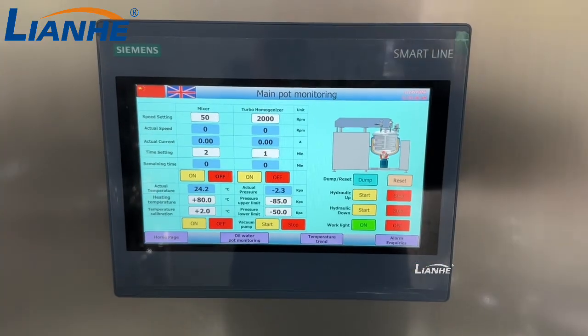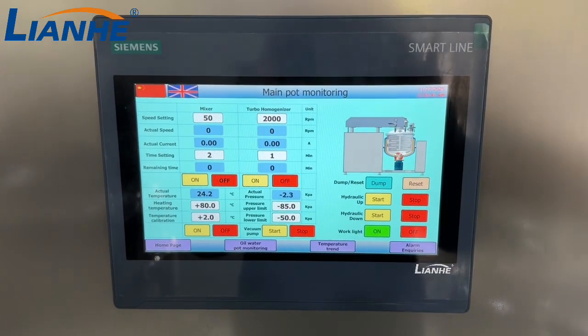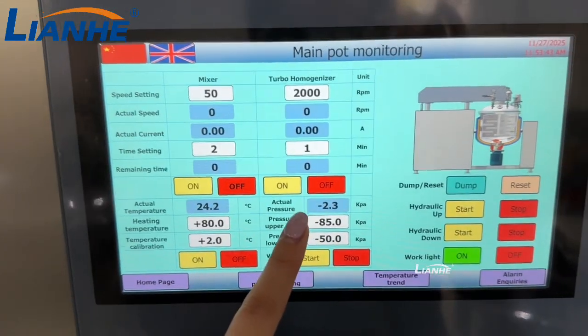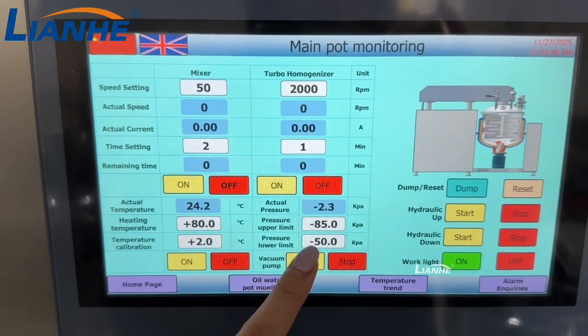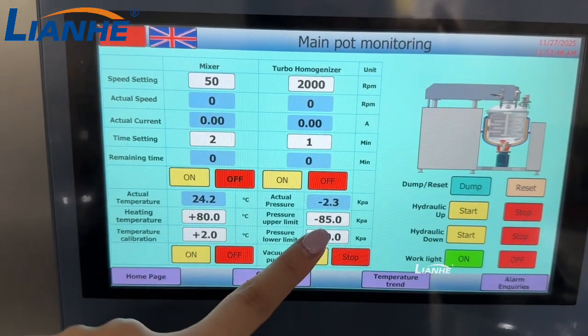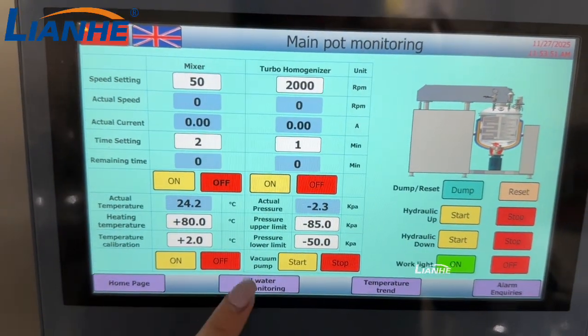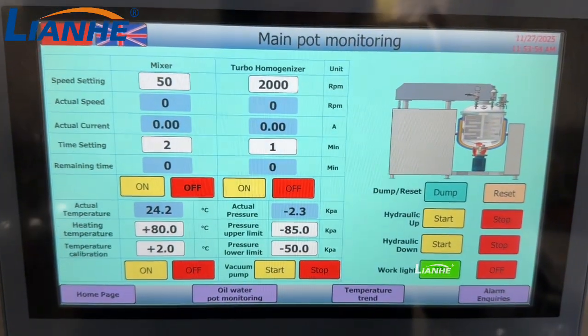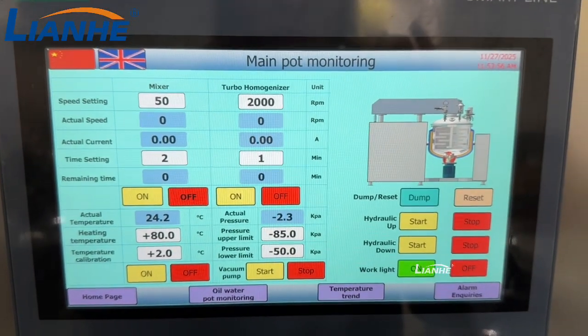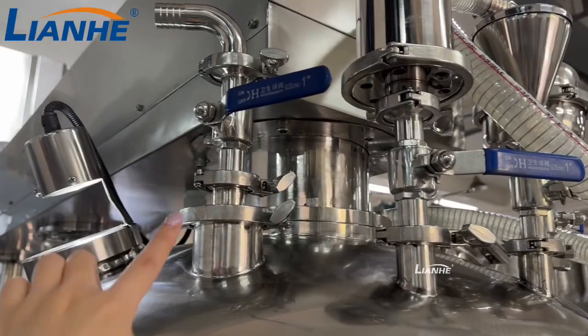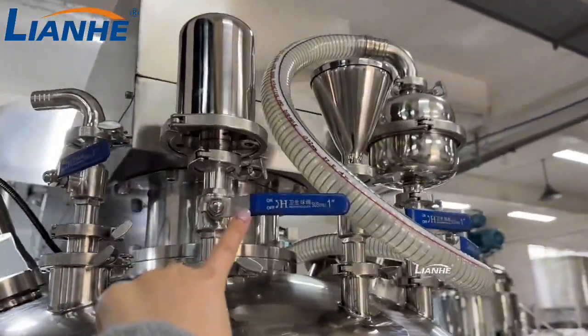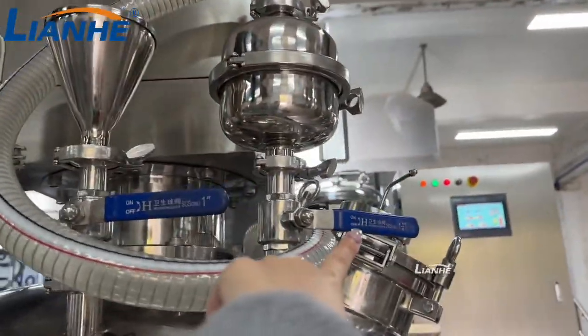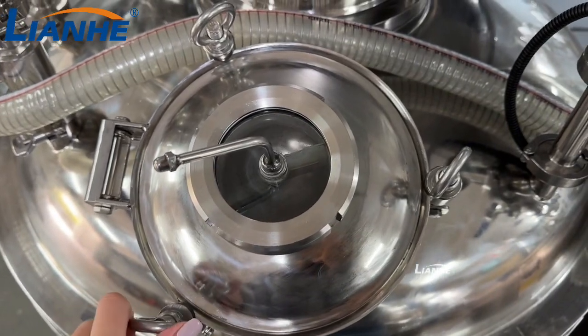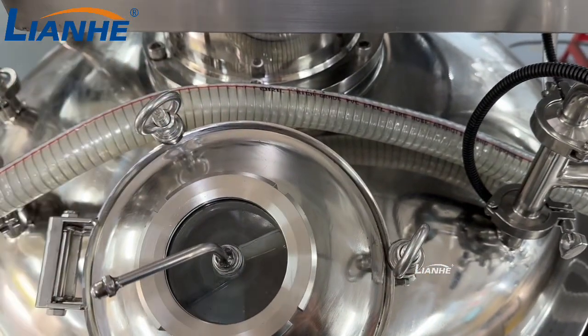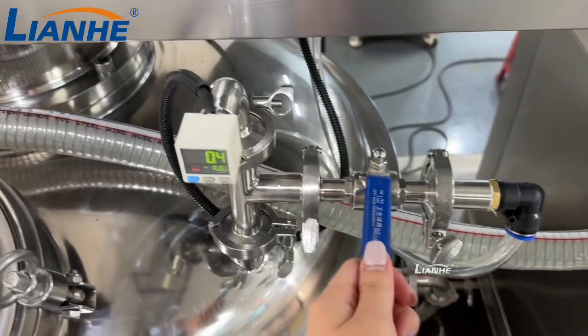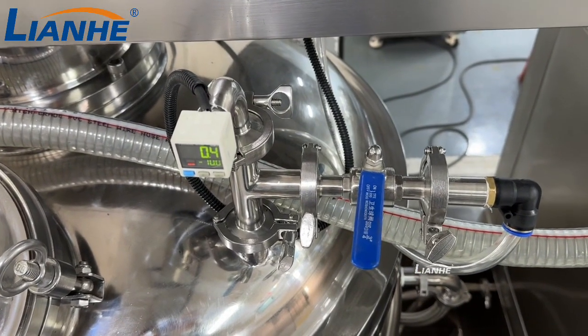And now we can test the machine's function step by step. First we can test the vacuum function. Now we already set the pressure of the vacuum, like minus 85 kPa, and the pressure lower limit is minus 50 kPa. And then we can check the valves. You may check these valves: closed, closed, closed, and closed. And also you may check this manhole is correctly closed. And then you can use this vacuum valve to use the vacuum function.